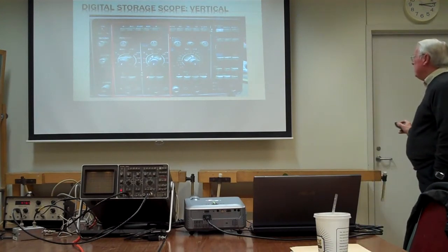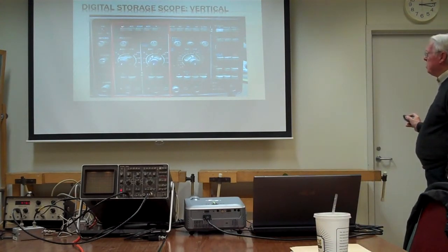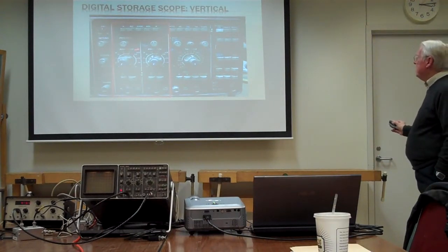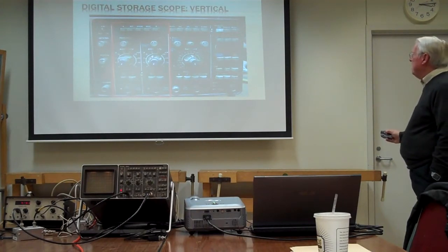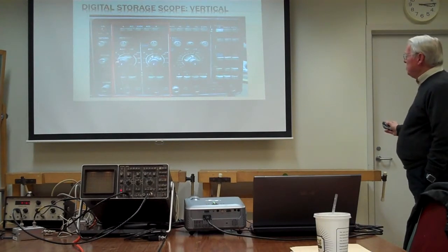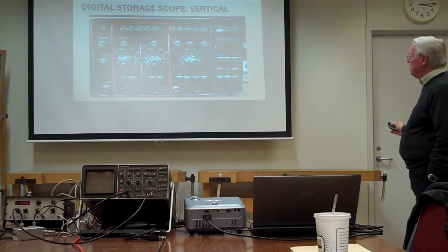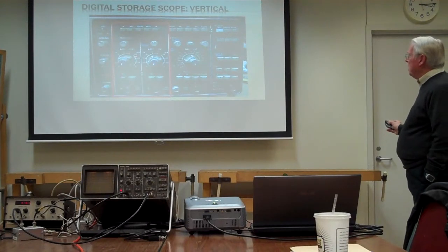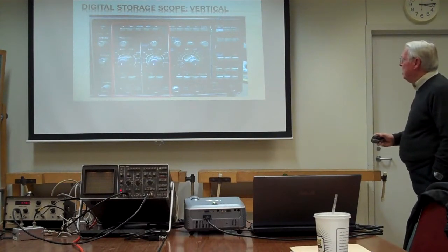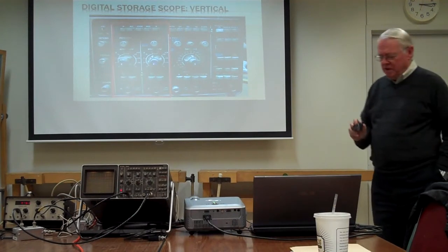Over on the vertical side, we have our switches. We can switch from A to alternate to chop to add to B modes. There's a knob to pull to invert the B channel, and we have our coupling down here - AC, DC, or ground, as we talked about. We also have the volts per division in the 1-2-5 sequence, and there's a variable control if you want something other than the step functions on the amplitude per division.